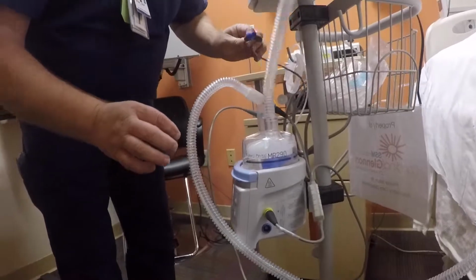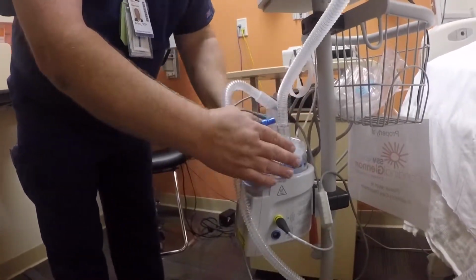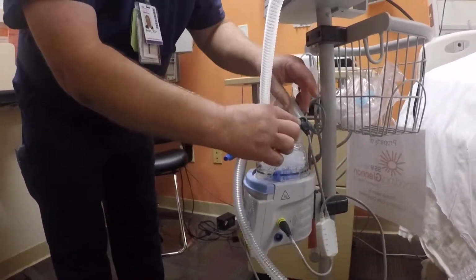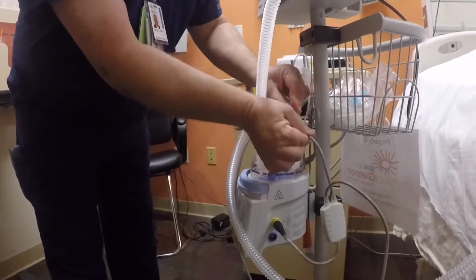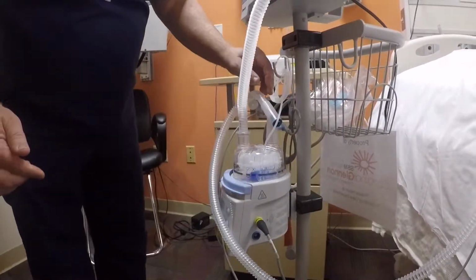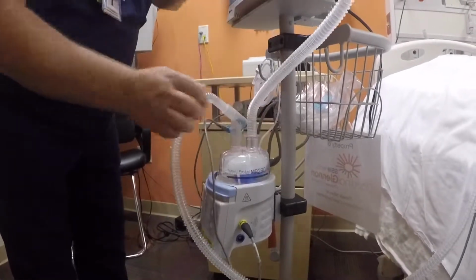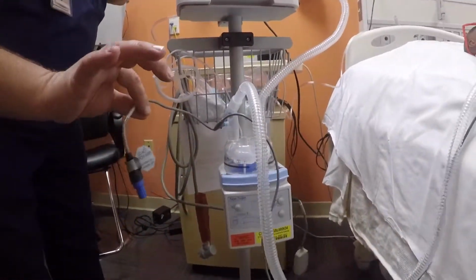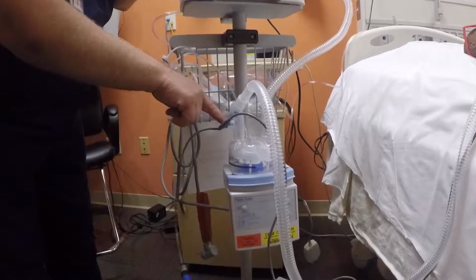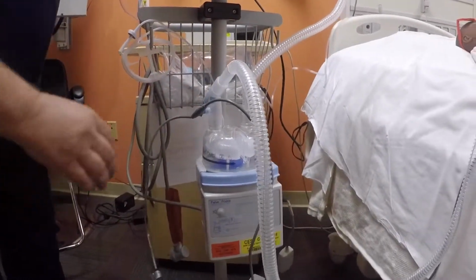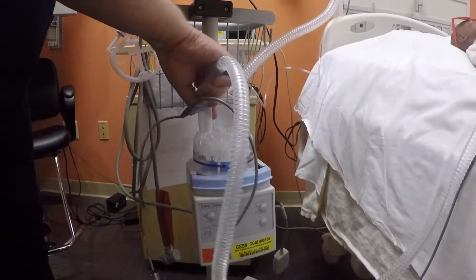A lot of times the easiest way, what I tell a lot of EMSs, is just disconnect the wire from the humidifier, and that way it can go. That would be the temp probe. This is the heater wire that'll need to be disconnected. We can just let that go. At that point, we're disconnected. We could go. You don't have to worry about replacing the cap in there. It keeps the circuit intact.